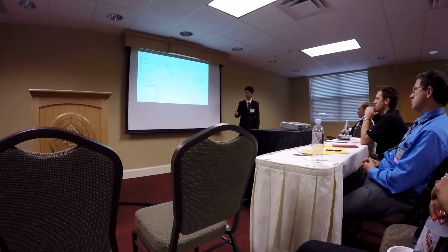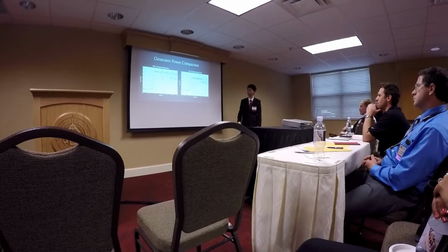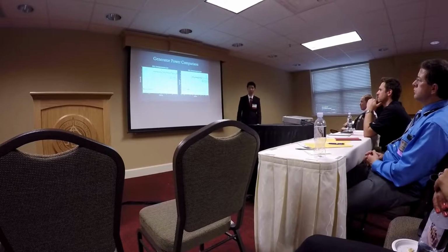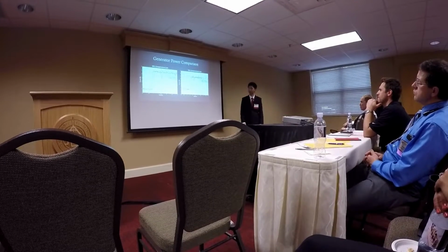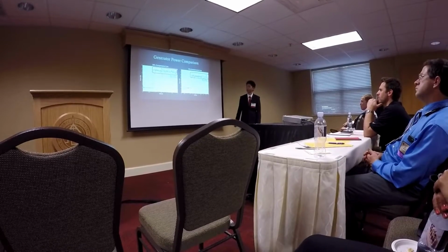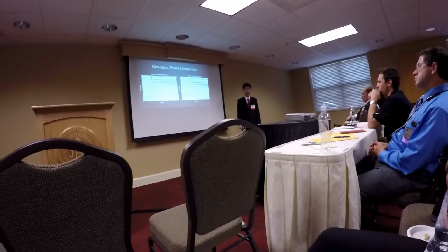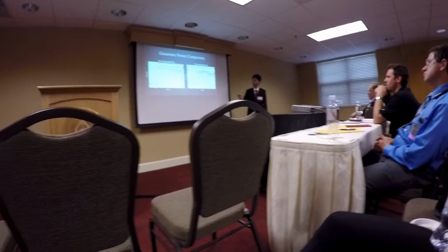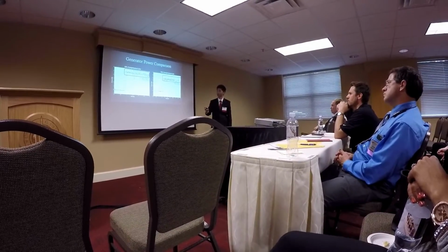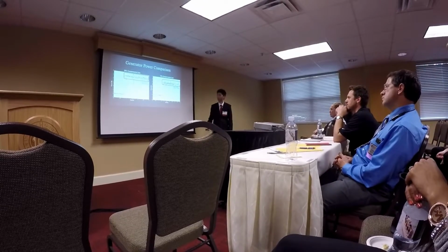And that's why here is the result for controller number 4 that we were able to capture for both the 50 and 70% compensated lines. You can see that the blue line is the power with the controller, which shows a reduction in subsynchronous resonance, while the red line shows without a controller, and you can see that there is quite a lot of resonance.